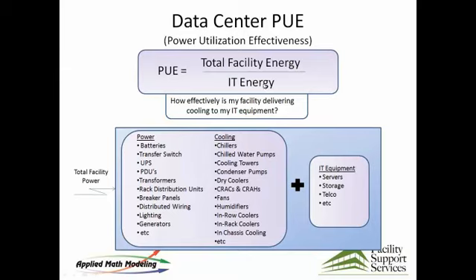Now these are measurements that you actually made. They're spot measurements, not an average, of course, Matt, but a spot measurement of current you made at the site, off the cooling units, correct? Correct. All we did there was a quick power calculation. It is instantaneous, not an average, and these things do vary over time. But nonetheless, what we find is that it's important to get some kind of measurement so that you know what ballpark you're in, where you are in general with respect to energy efficiency.